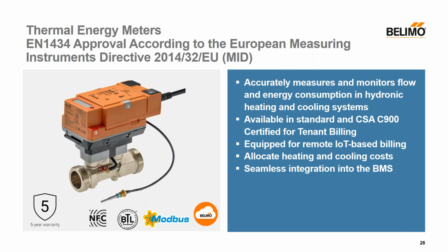It's equipped for remote IoT-based billing, which allows for effectively allocating heating and cooling costs, allows to inform building operators and tenants of energy that is added or removed from each unit, and seamlessly integrate this thermal energy data into the BMS. It also comes with its own digital calibration certificate. They're offered in NEMA 4X options. The MID CSA C900 models are going to release later in Q2. They're not in the printed PGPL, but will be added to the digital version when they become available.